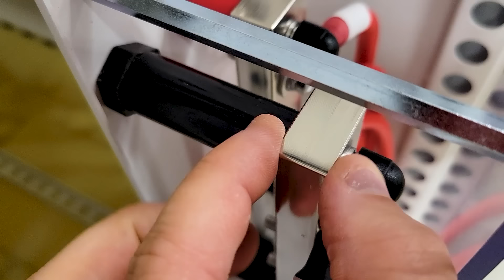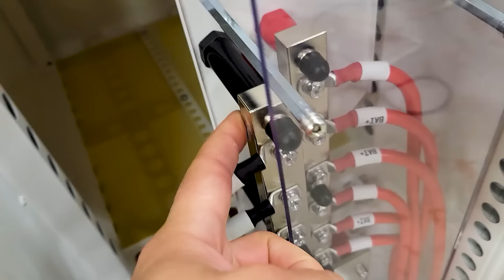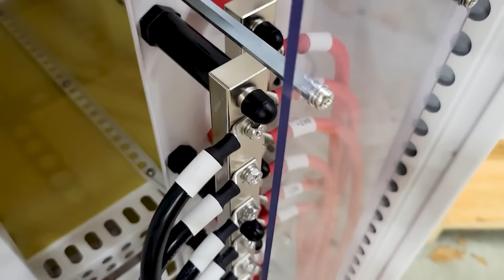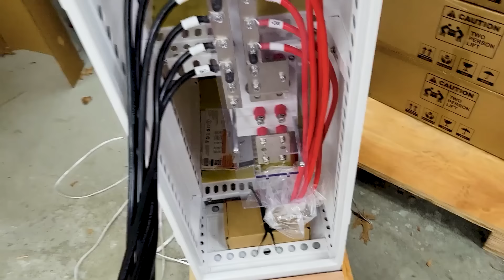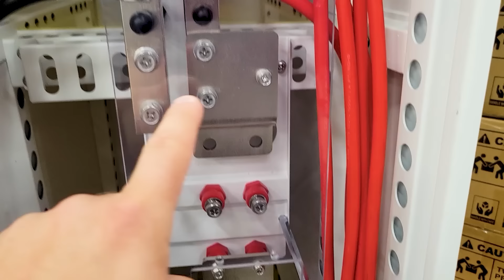Wow, that is beefy. I'll have to get a measure on that, but that's a pretty beefy bus bar. They look like they have nylon standoffs off the back. And looks like we have our 6 wires. Each wire has its own Amphenol connector on there and comes back to the bus bar. Very nice. It looks like they're all equal length wires, so we should be able to pull from the batteries equally. We have our positive wires coming down, and then I think right here is where the circuit breaker is going to wind up sitting, between that positive bus bar and that one.